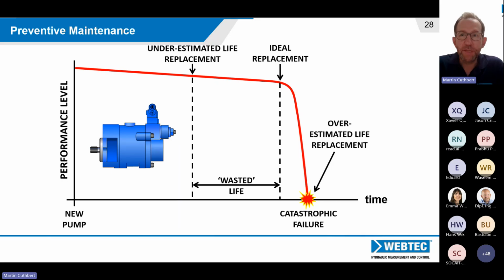So from a preventive maintenance point of view, what you'd be aiming to do is to take tests over time. Let's say that time period shown there is 10 years. You'd be taking points every sort of 6 to 12 months along there to look at how the pump is performing compared with last time and compared with the manufacturer's specification. And that would give you some idea of where you are on that curve and give you an indication of really what the life of that pump is.